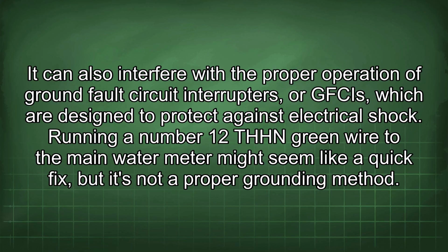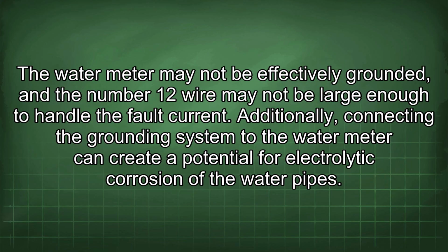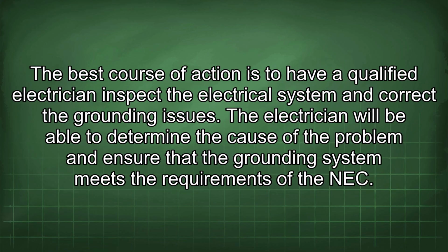Running a number 12 THHN green wire to the main water meter might seem like a quick fix, but it's not a proper grounding method. The water meter may not be effectively grounded, and the number 12 wire may not be large enough to handle the fault current. Additionally, connecting the grounding system to the water meter can create a potential for electrolytic corrosion of the water pipes.